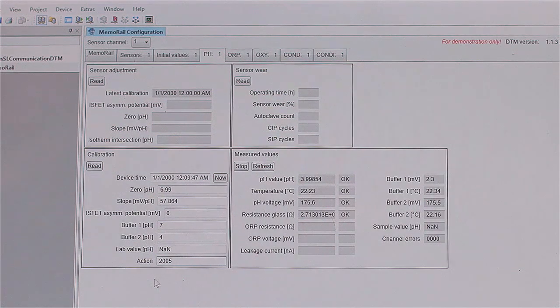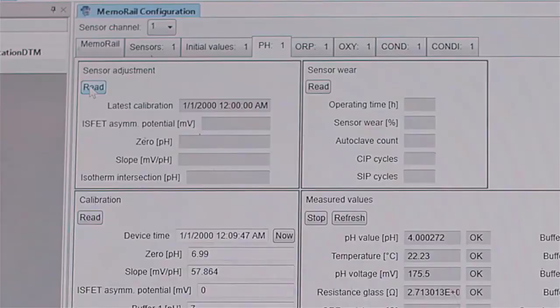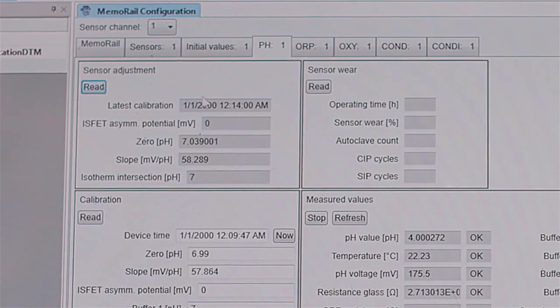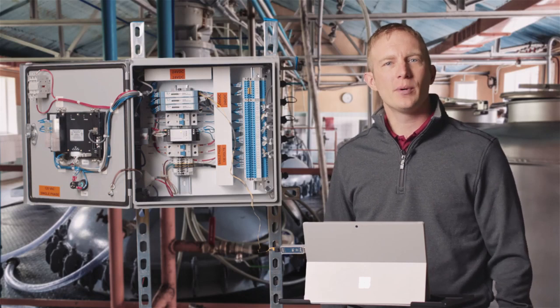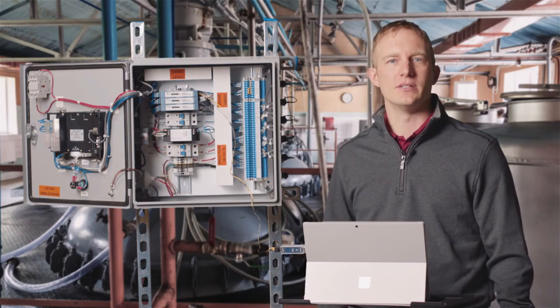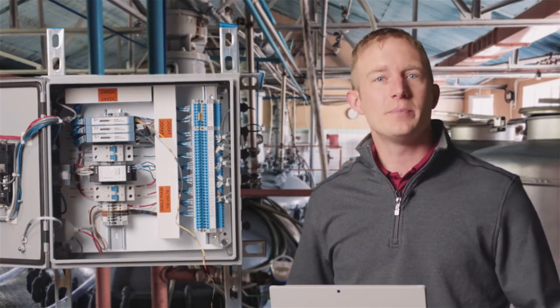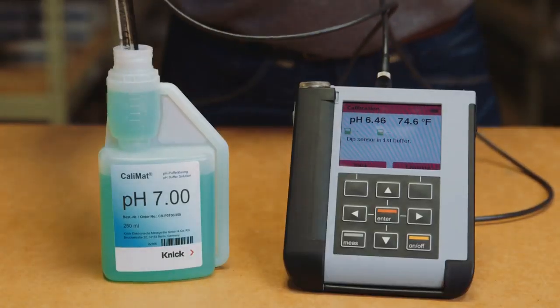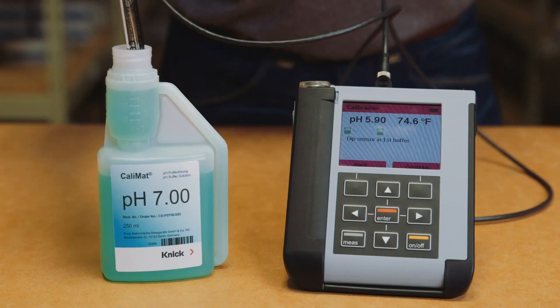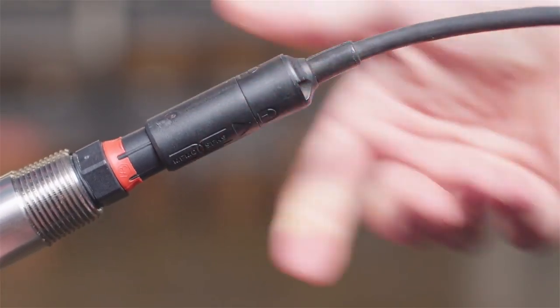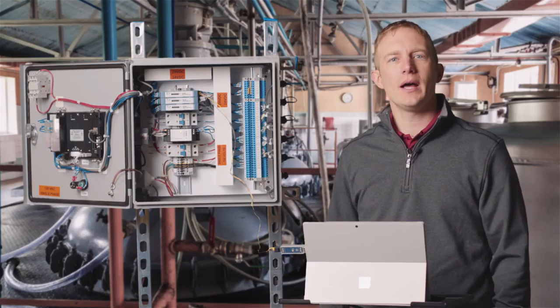We can now click Read under the Sensor Adjustment tab in the DTM to view our calibration status. This concludes our 2-point calibration of our MemoSense pH sensor using MemoRail Modbus. Note that calibrations can always be conducted offline using the Knick Portavo series portable meter. We're now ready to reinstall our sensor and go online with our measurement.